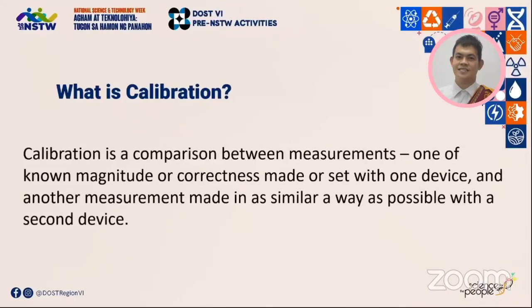Calibration can be briefly described as an activity where the instrument being tested is compared to a known reference value. At the simplest level, calibration is a comparison between measurements — one of known magnitude or correctness made with one device, and another measurement made in as similar a way as possible with a second device. The device with known or assigned correctness is called the standard, while the second device is the unit under test or test instrument.